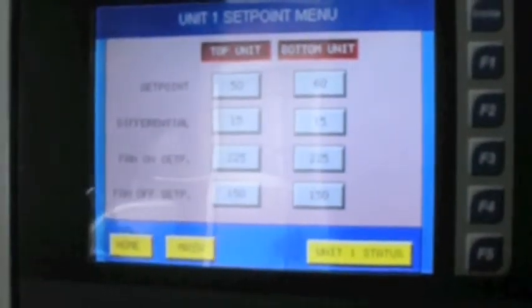You also have your set point page. This is where the chiller turns off, is the set point. So Unit 1, the top unit, will cool until the water reaches 50. It turns off until it warms up to the differential, which would be 50 plus 15, which is 65 degrees, and it will turn back on again. The fan on and off set points are factory set. They are adjustable in case we need to make some changes in the field.